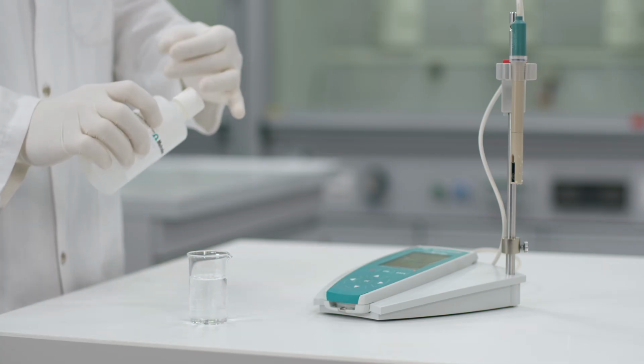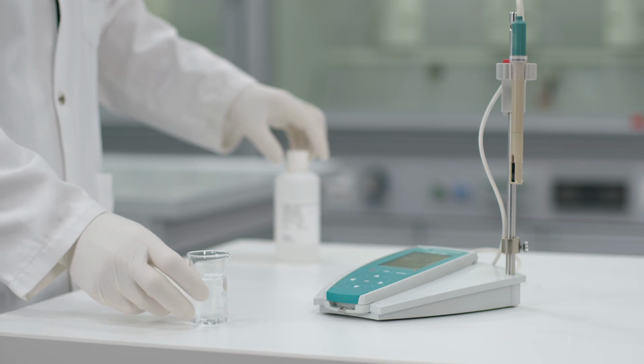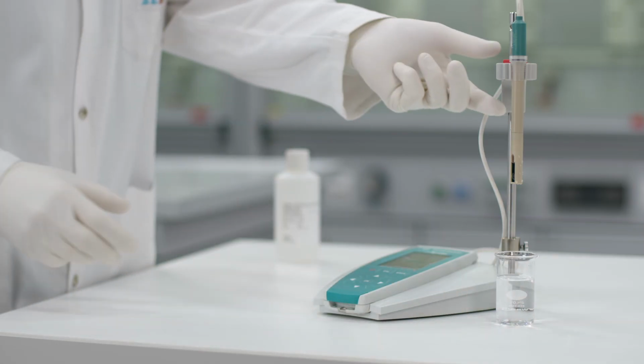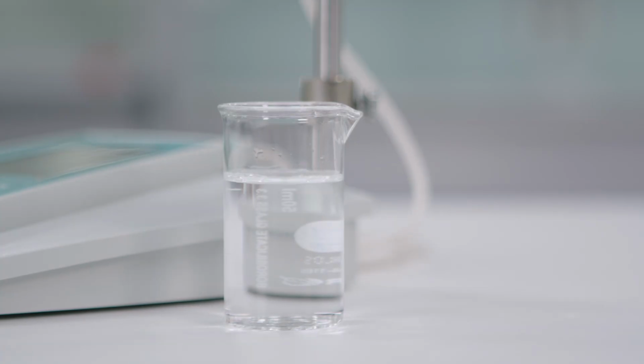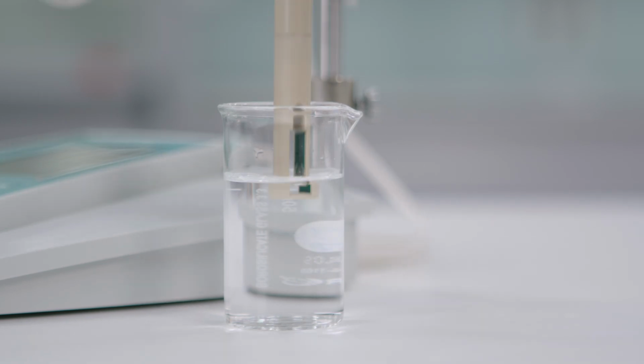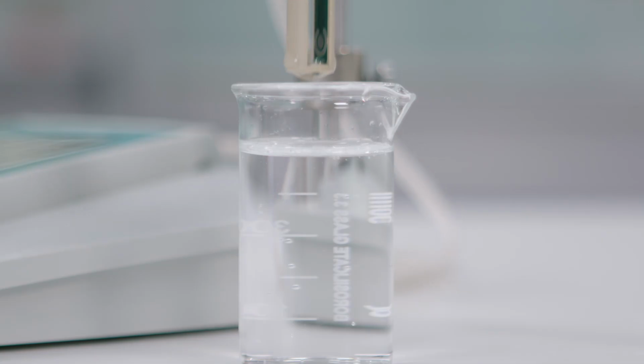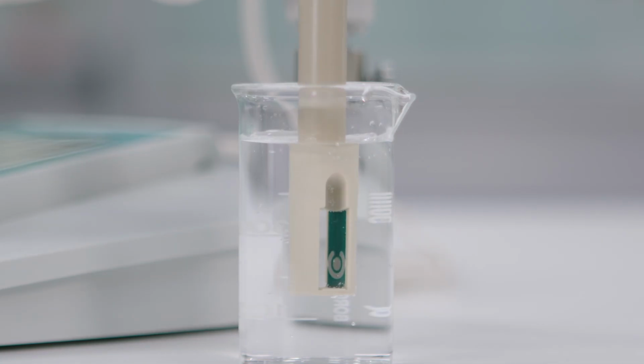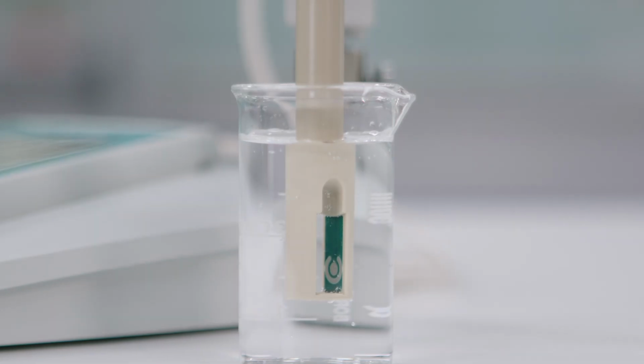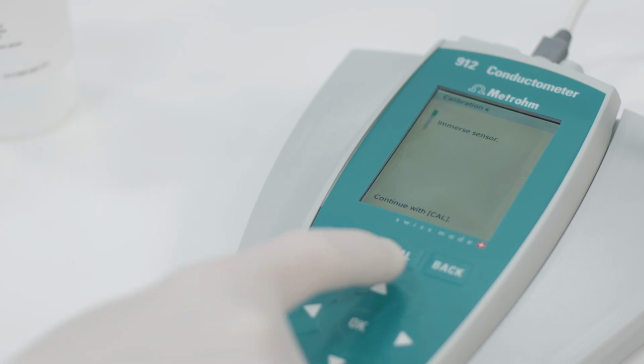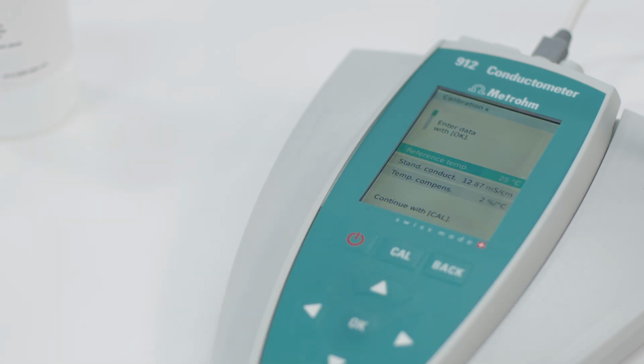Immerse the conductivity measuring cell into the standard solution. Dip it 3 times to get rid of any air bubbles that could stick to the surface. Make sure the measuring cell is fully submerged up to the hole and there are no air bubbles trapped within the measuring cell. Trapped air will cause incorrect readings. Confirm the immersion by pressing cal.